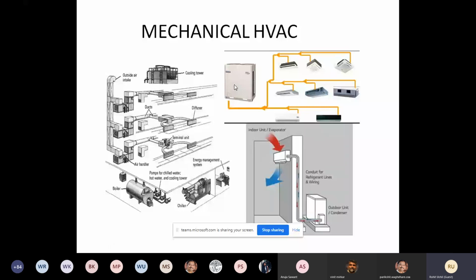The benefit of this kind of system is that you don't have outdoor units everywhere. If you see a normal residential building nowadays, there are split units everywhere, and on the facade or in the shaft you will see multiple outdoor units placed. The reason is that the indoor units are multiple, and hence you have multiple outdoor units also. With a variable refrigerant flow system, you have only one outdoor unit for maybe 12, 15, 20 indoor units. And in the case of apartments, maybe there'll be one outdoor unit for each apartment.